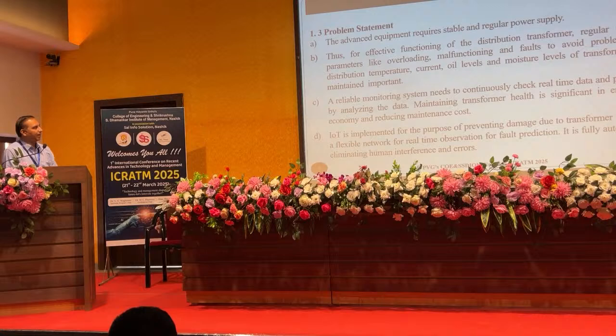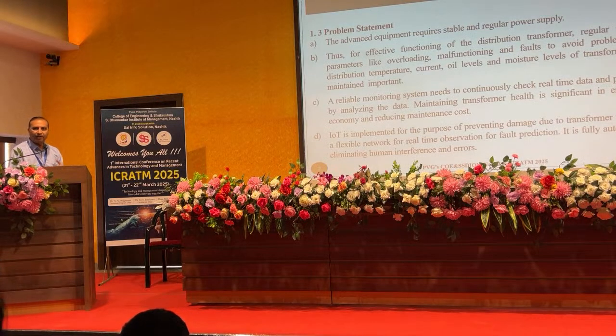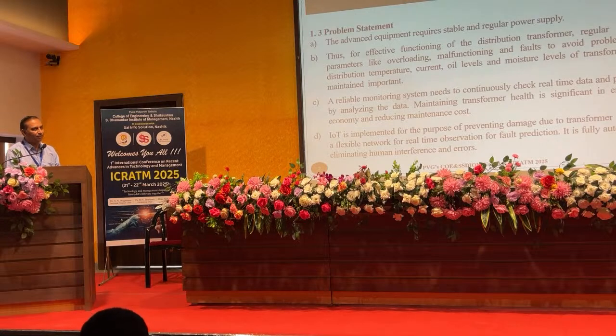Regular monitoring of the parameters is required so that overloading, malfunctioning and the faults which can occur in the transformer can be prevented, which can occur because of temperature increase, current levels or oil level. Sometimes the oil level drastically drops down and then the transformer heating takes place. As the temperature goes beyond a certain limit, automatically the transformer is going to fail because of excessive heating. For preventing the temperature failure, we are using oil cooling systems. If the oil level goes down, automatically this will relate to the failure of the transformer. So the main thing is to determine the oil level.